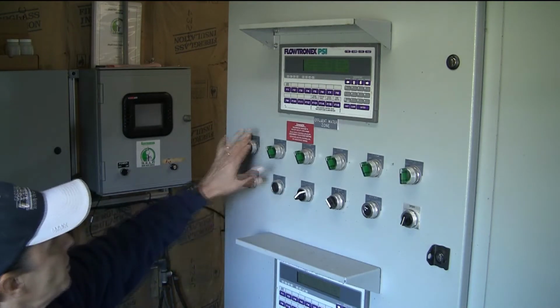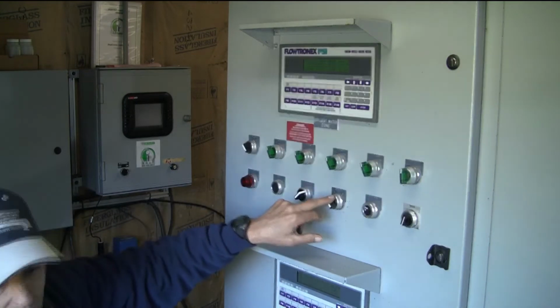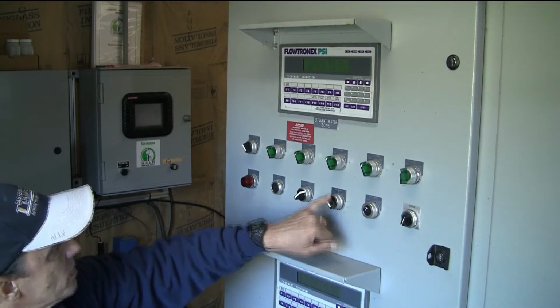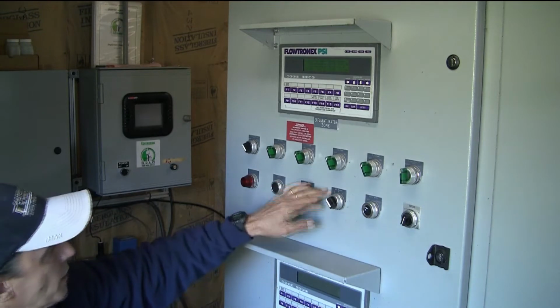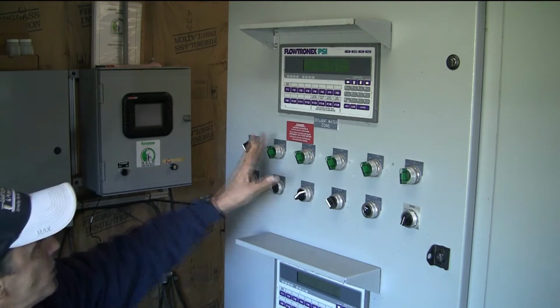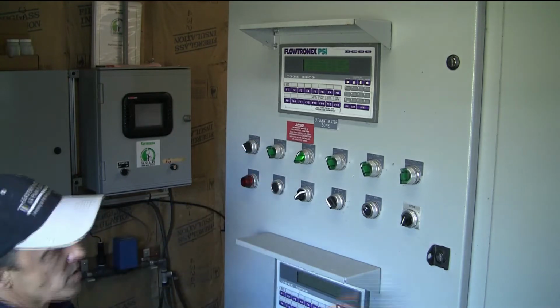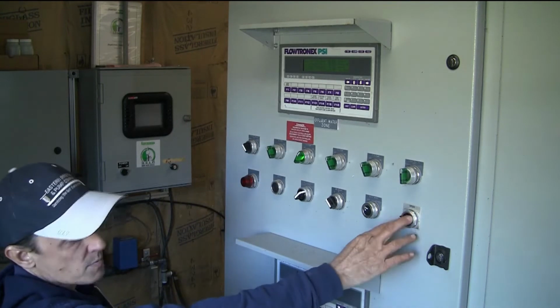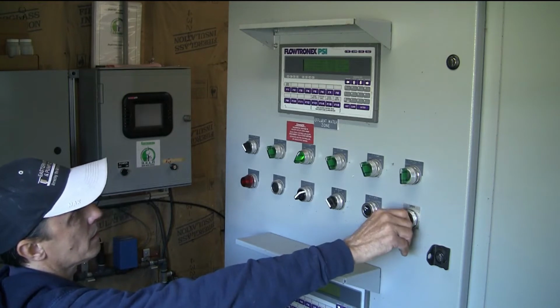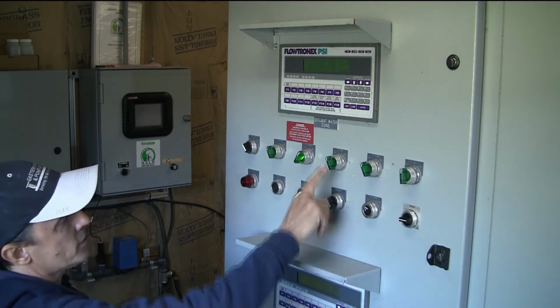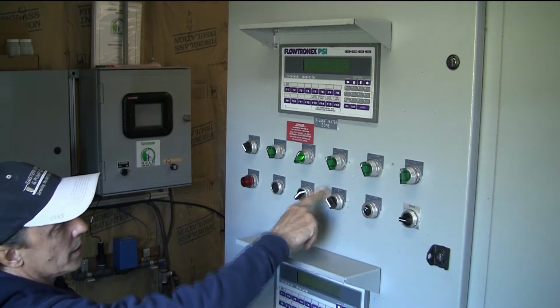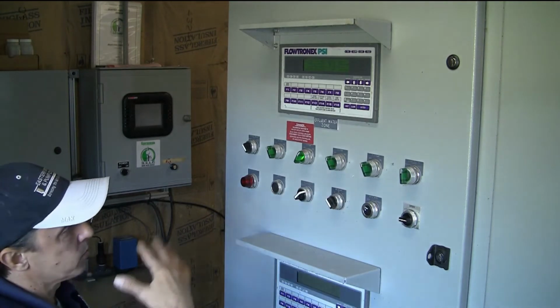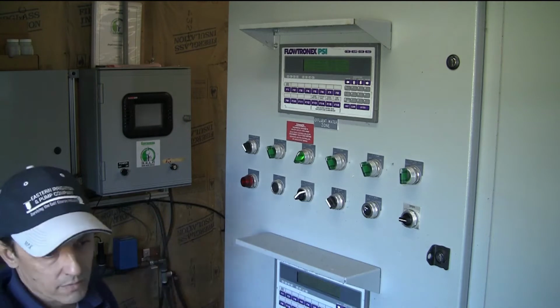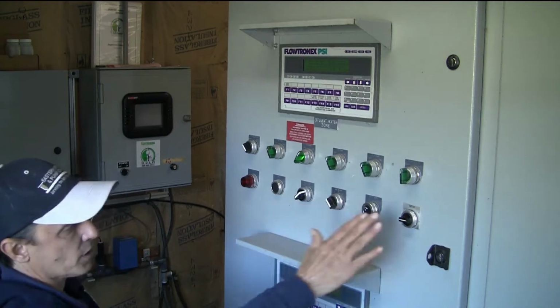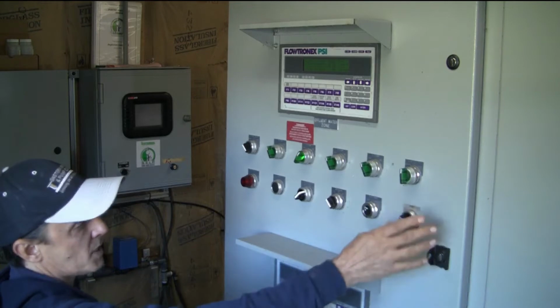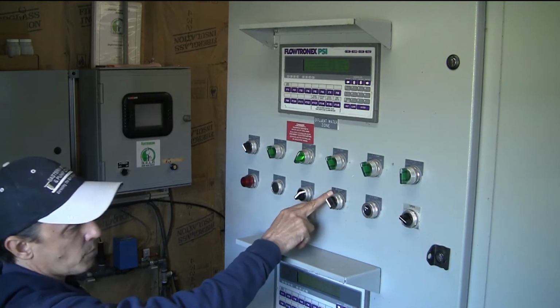So I'll put it in manual, and there is a VFD select switch that's used in manual operation. Right now I have it pointed to number 1, so if I turn number 1 on, it'll start very slow, and I'll be able to control it with the speed pot. If I turn 2 or 3 on, those will come on full speed. So if you're going to ever do any testing, and you're going to use the VFD speed pot, you want to make sure you have it pointed to the number of the pump you want to turn on.